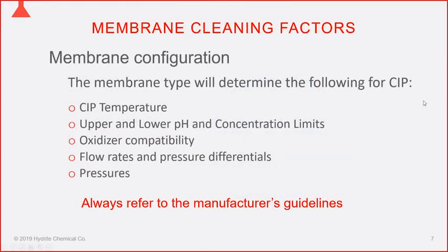Regarding membrane configuration: the type of membrane dictates a lot about how we'll clean the system. Most membranes we encounter are standard membranes that can tolerate 120–125°F CIP temperature, though high-temperature membranes are being used more. Membranes generally have similar upper and lower pH and concentration limits — low pH from membrane suppliers is typically 2.0, sometimes stretched to 1.8, and the upper limits are generally around 11.